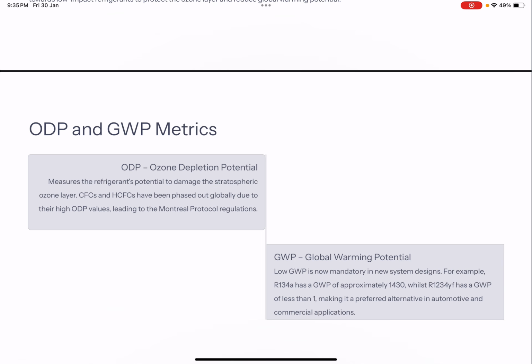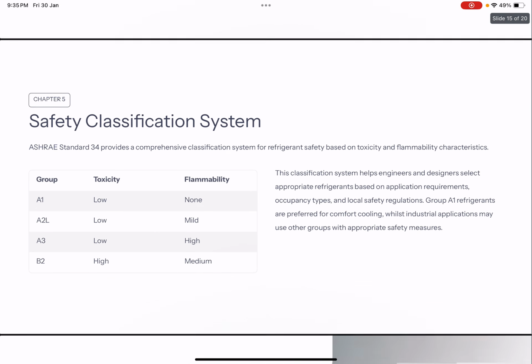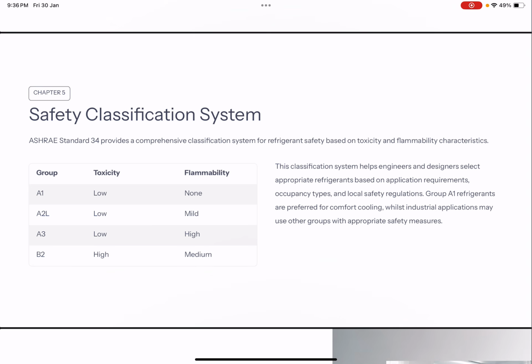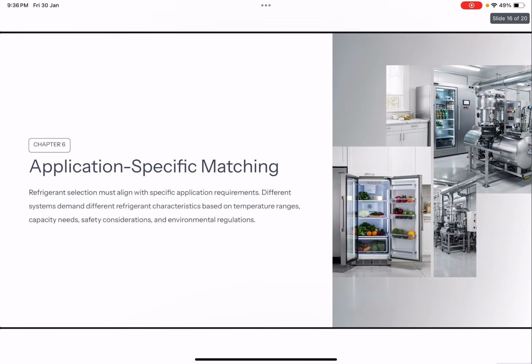For example, R134a has a GWP of approximately 1430, while R1234yf has a global warming potential which is less than 1. So from a global warming potential perspective, instead of R134a, R1234yf is the desirable refrigerant. As I mentioned earlier about the safety classification, if toxicity is low and flammability is none, that comes under the safest refrigerant category, A1. And if the toxicity is high and the flammability is medium, that comes under group B2. Similarly, A3, A2L categorization is provided here on this slide, and this classification is based on the ASHRAE rating.